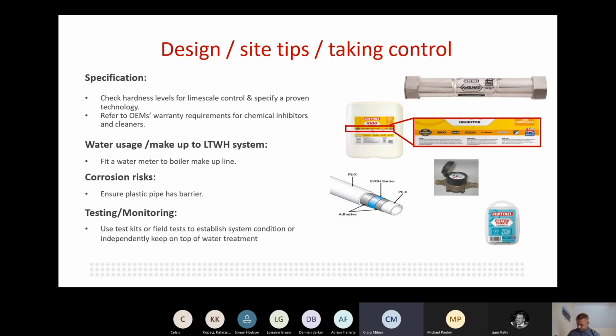Other areas are making sure pump flanges are tight - we do get a lot of pumps sucking air in. Make sure you're using a quality product. Best bit of advice: if you're not going to specify one particular thing, just make sure it complies with the boiler manufacturer's warranties. That's your best get-out, and then they've got no comeback if you do have a complaint. Make sure that what you're using for treatment on your closed heating systems is covered by the boiler manufacturer - it'll protect you more than anything.